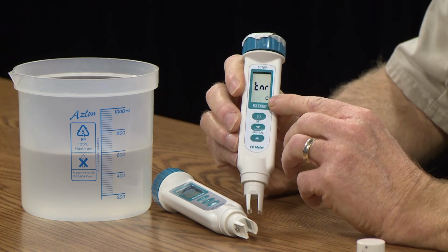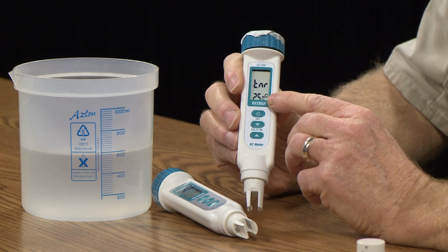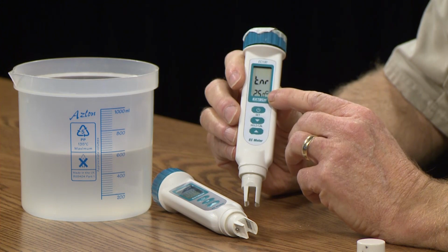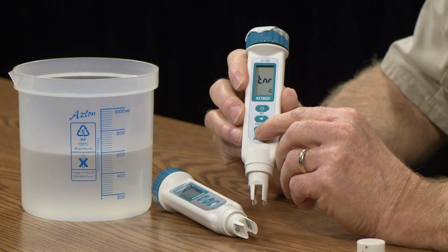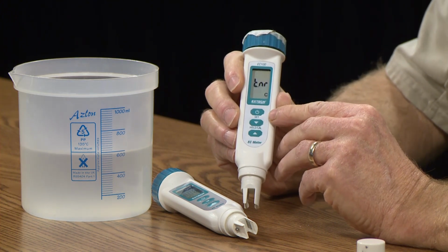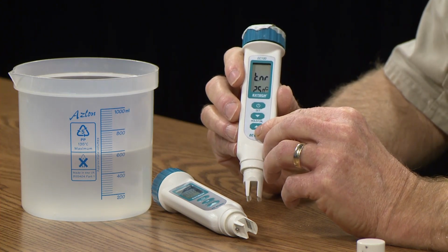This is the specific temperature that you can set. So in this case, if you were taking specific conductivity, it would be referenced to 25 degrees. I could reference it to 20 degrees if I wanted to, but typically, more commonly, 25 degrees. So that's what that is. So this is set up for a specific conductivity to 25 degrees.